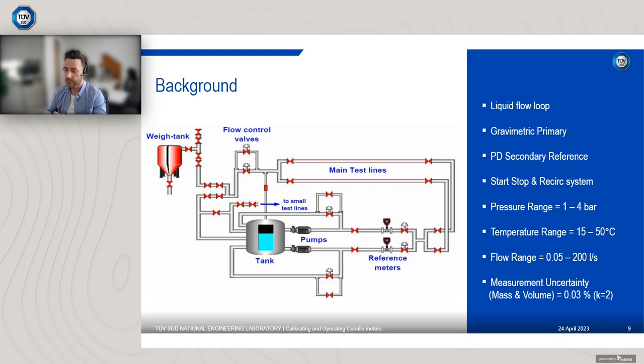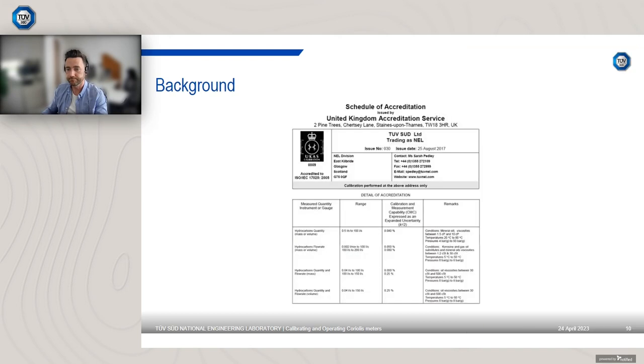So this is for fluids below 20 centipoise. Above 20 centipoise, our measurement uncertainty is higher. For mass, it's 0.05%, and for volume, it's 0.25%. And this is our UKAS schedule. So just to show you, facilities are fully accredited. We have our CMC, so that's our calibration and measurement capability, expressed as an expanded uncertainty, in this case k equals 2. And it also has all the various remarks with regard to the conditions, so the viscosities, temperature ranges, and you can see the flow ranges as well, and then details your measurement uncertainty.